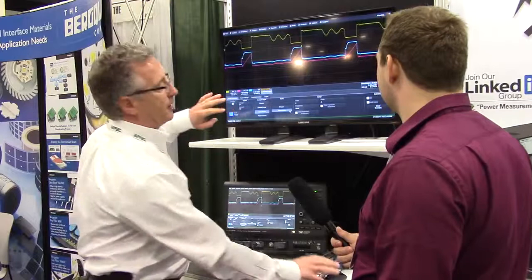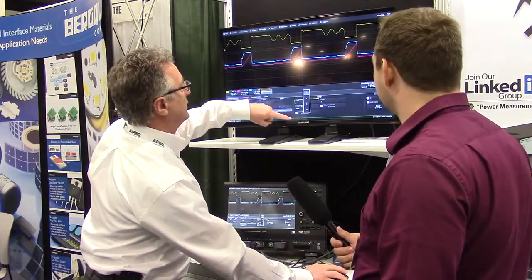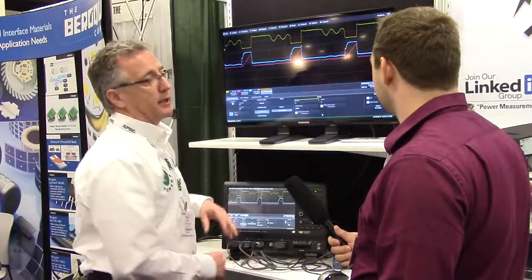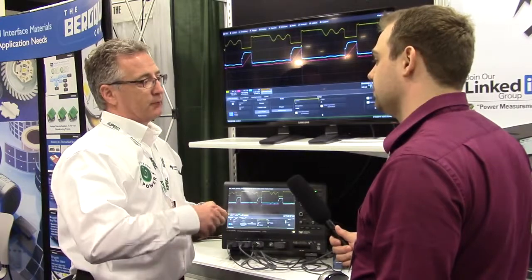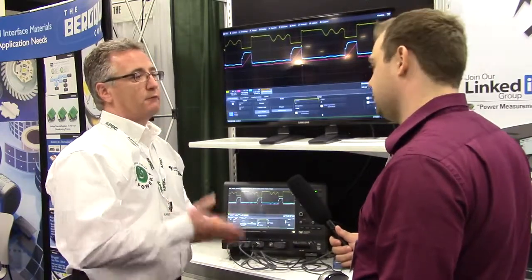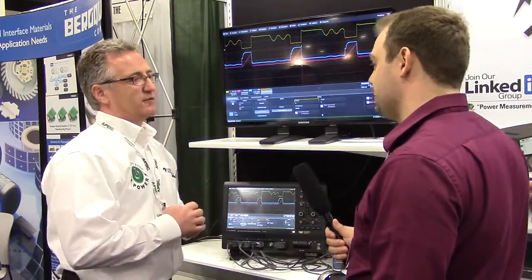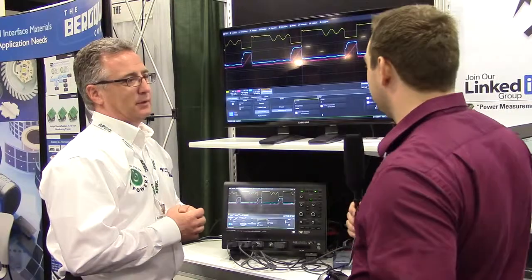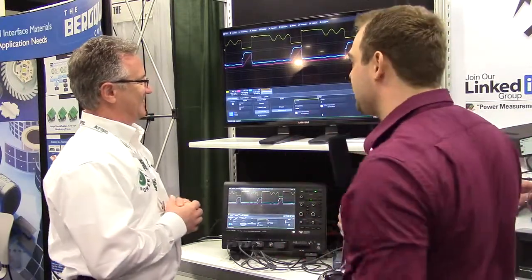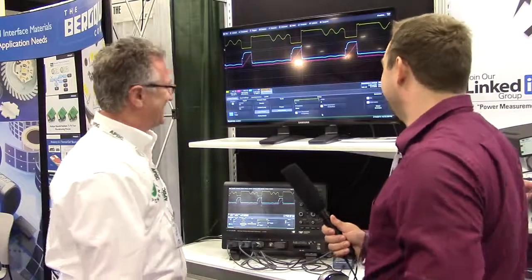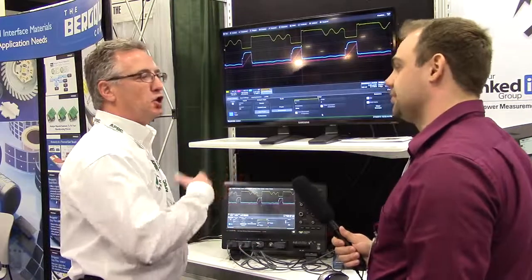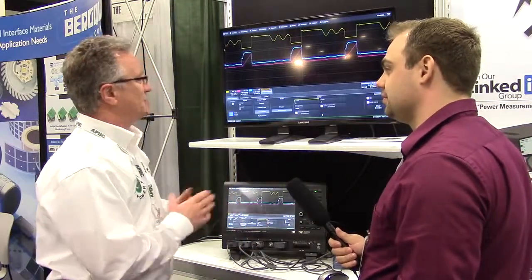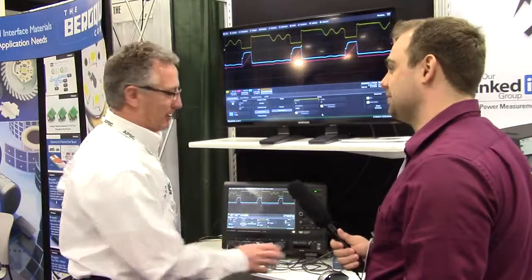So we've got that all set up for each of the classes, and we'll create an FFT display that shows for up to the 40th harmonic what the current harmonics are for each one of those, and whether they exceed or pass for each of those harmonics. Very nice, and as a European, I love that the standard frequency preset is 50 hertz. That's right, yes. I've had a chance to work with European, Asian, and U.S. environments, and we have to have our software support all of that.